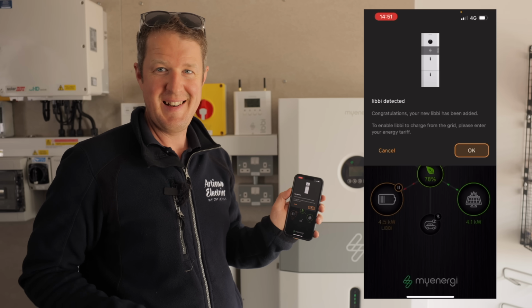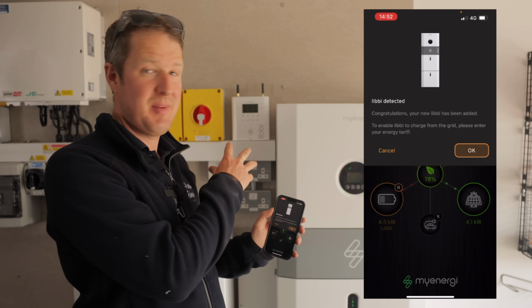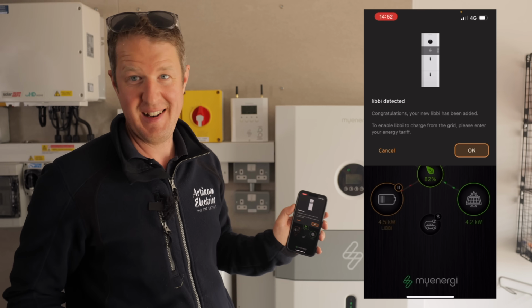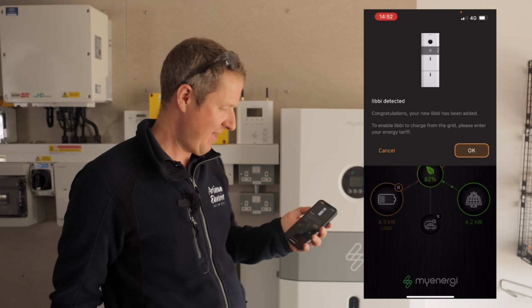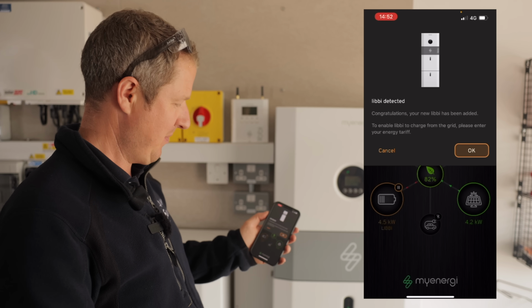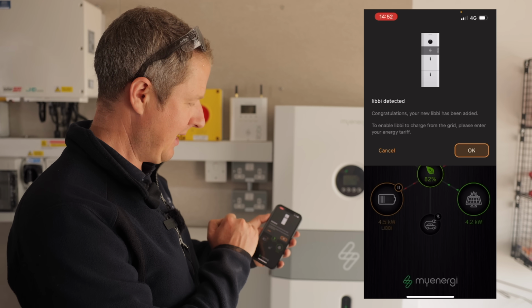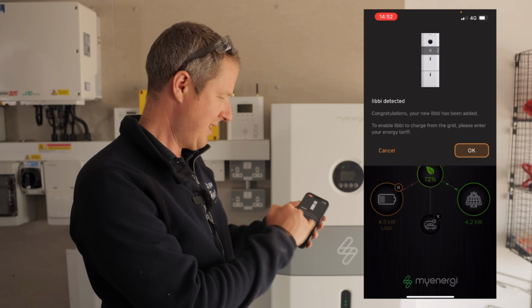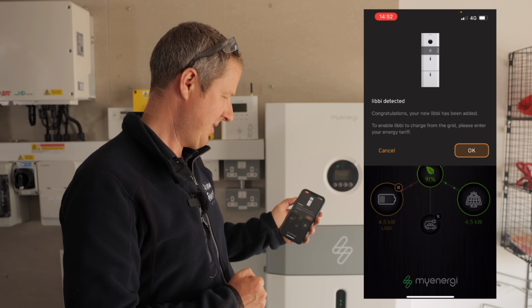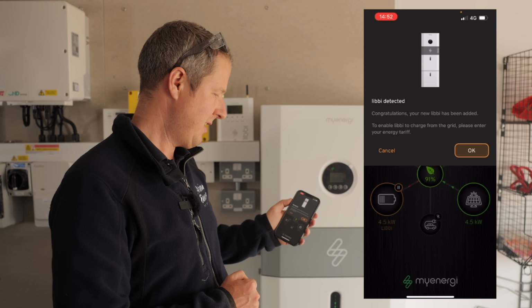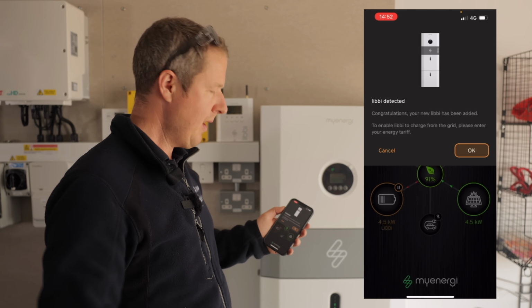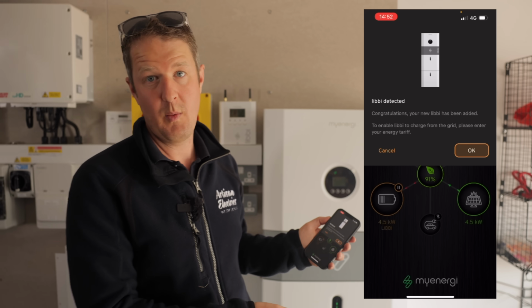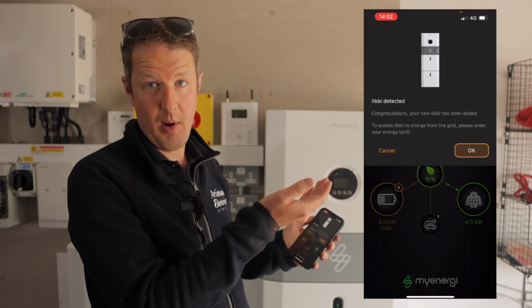But we'll remove the export limit on the SolarEdge inverter, and then you'll see that it'll constantly be generating 8 kilowatts. Now that we've got everything paired up between each other, we're going to check on the MyEnergi app to make sure that the Libbi's appearing there. And it has appeared, it says Libbi detected, and gives you a little startup message: Congratulations, your new Libbi has been added. To enable Libbi to charge from the grid, please enter your energy tariff.